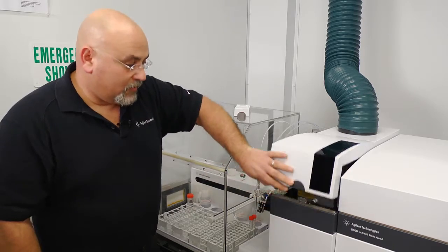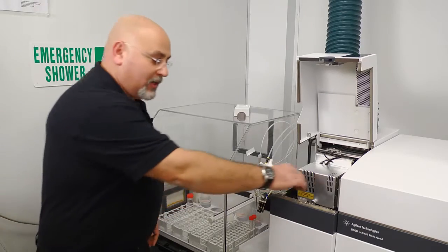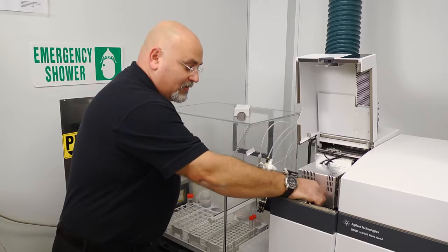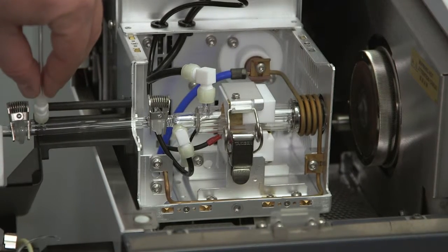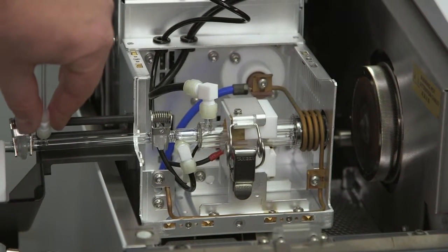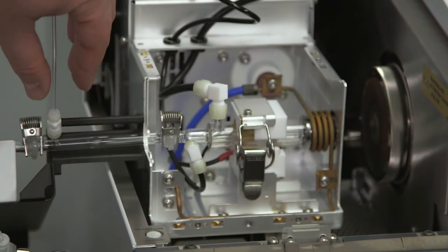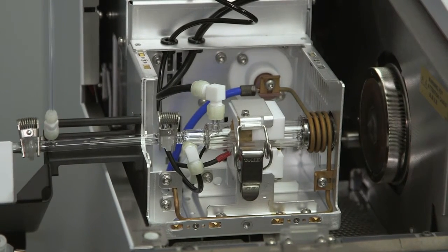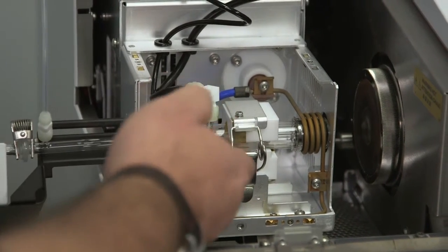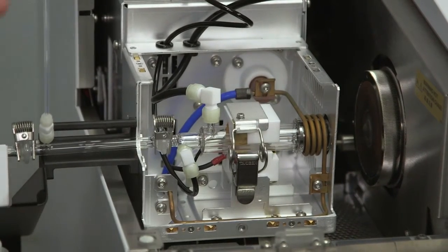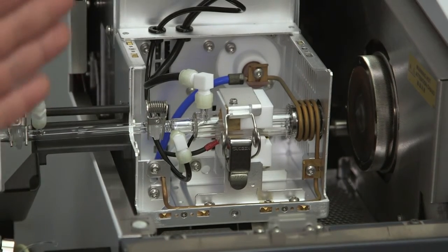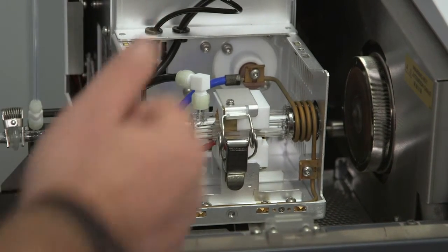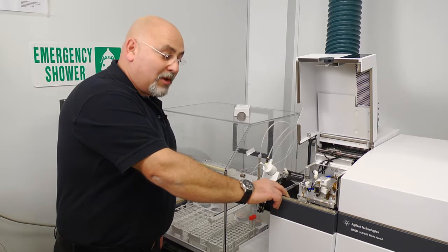I will now open the latch to show a closer look at the inside of the sample introduction. Right up front, we can see the high matrix interface, which allows you to do aerosol dilutions, a high capability of any of the Agilent ICP-MSs. We are then looking at the torch, and we see the 2 gases: the plasma gas and the auxiliary gas. Fairly simple, and all really easy to dismount and mount back.